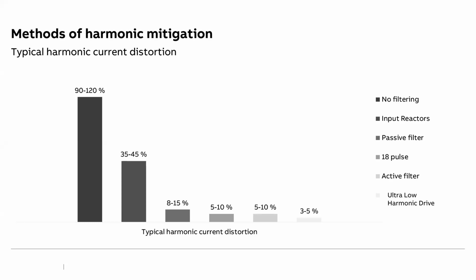Now, if we have to go below 30%, say to achieve a 5% or 10% level of harmonics, then we need some additional devices, some additional filters. There are various filters available in the market. There are basically two types: passive filters and active filters. A passive filter is equipment which has a fixed impedance value and is designed for a particular load condition. Then there are active filters. An active filter, as the name suggests, has an active component inbuilt, so it injects a reverse signal that cancels out the resultant harmonic. With these filters, we can achieve harmonics of up to 5% or 10% as per the requirement.